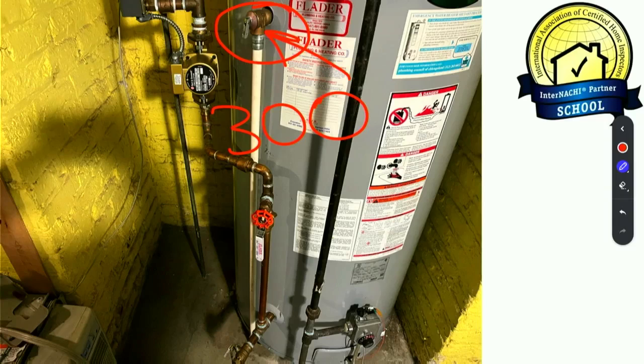And things have to go wrong. We have to have a lot of planets in alignment for things to go wrong. My flame and temperature sensing has to turn the fire on, and then that has to fail and be locked in the flame-open position. Then it's got to keep cooking and cooking. And then I've got to be blocking my pressure relief valve. I can't let stuff like that release the pressure. And then the tank is going to rupture.